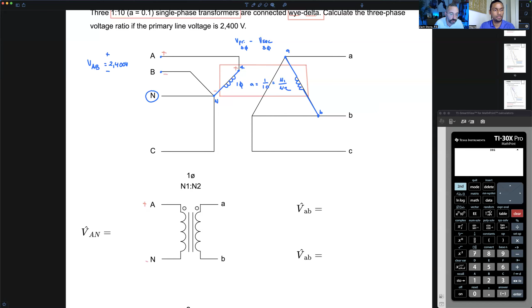How do we figure out the voltage applied directly across the primary winding from capital A to capital neutral of this single phase transformer? That's going to be the 2400 divided by root 3. Yeah, you got it - we're going from line voltage A to B to the phase voltage from A to neutral, so we take our line voltage, 2400 volts, and divide it by square root of 3.